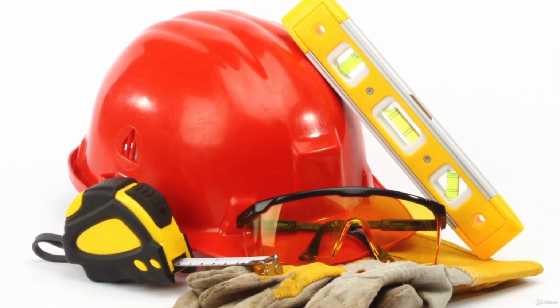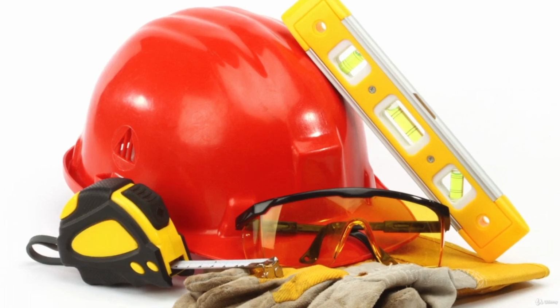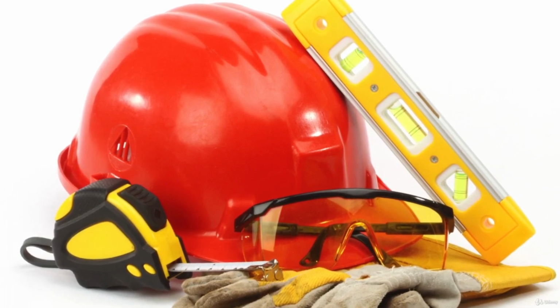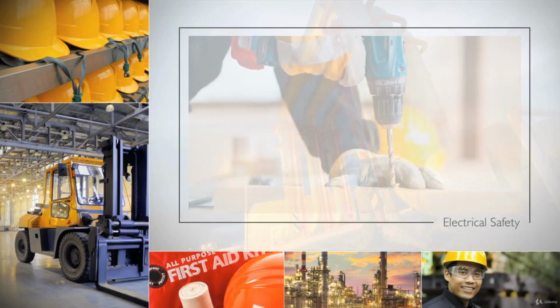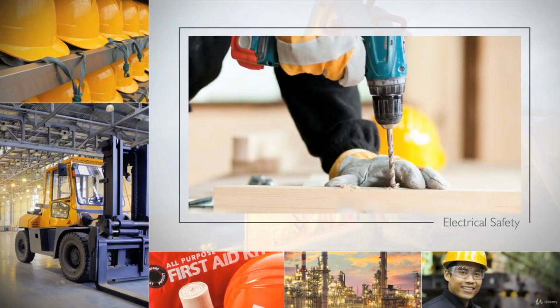OSHA also has requirements for grounding paths. Any path to ground circuits, equipment, and enclosures must be permanent and continuous. Handheld electrical tools can also pose danger to workers due to their continuous contact with their hands, so OSHA has created specific standards for protection. For instance, power drills use 30 times the current, which can kill a person. For adequate protection, tools must have a 3-wire cord with ground and be plugged into a grounded receptacle or be double insulated or powered by a low-voltage isolation transformer.